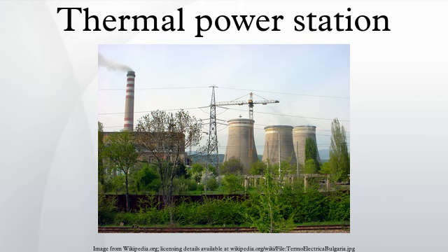Plants that use gas turbines to heat the water for conversion into steam use boilers known as heat recovery steam generators. The exhaust heat from the gas turbines is used to make superheated steam that is then used in a conventional water steam generation cycle, as described in gas turbine combined cycle plants section below. Boiler furnace and steam drum.